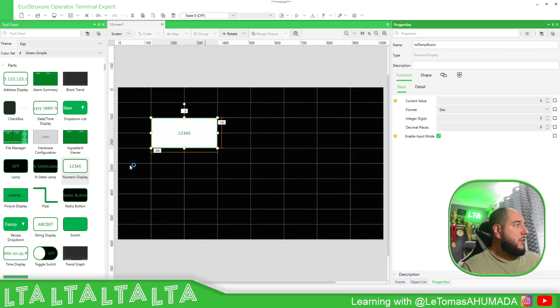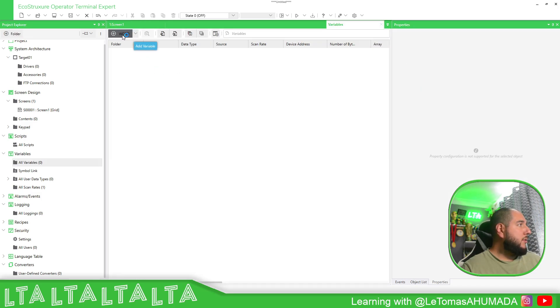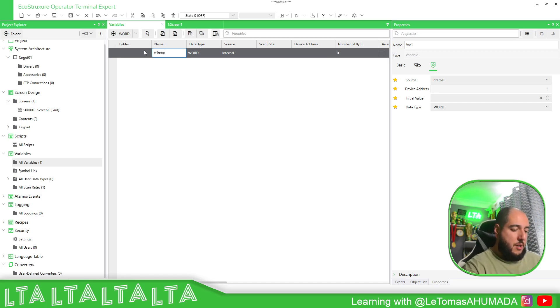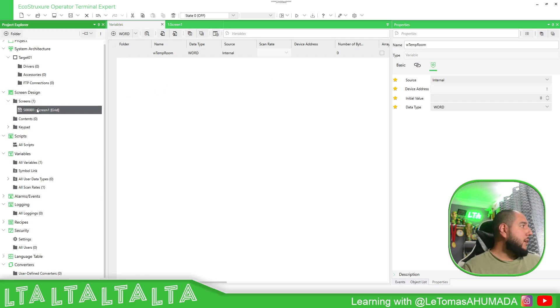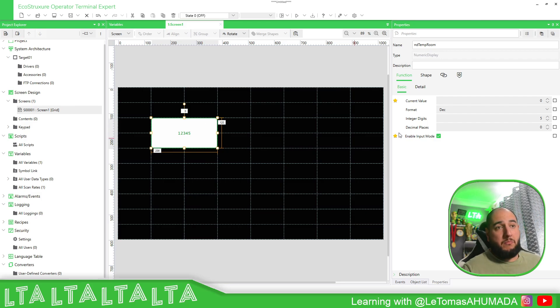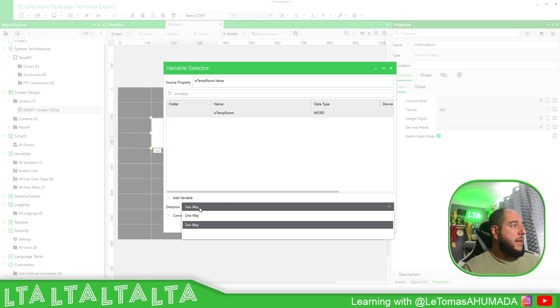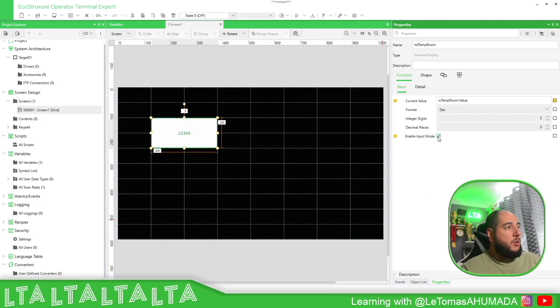By default, what we're going to use is Variables, and here you're able to see all the different variables. If you don't know how to create a variable, go to Project Explorer, then Variables — you should be able to find them. In this case it's internal, but you can import information from other PLCs. I'll select the variable 'Variable Temp Room.' Here we have the option to select one-way or two-way — basically read-only or read-write.